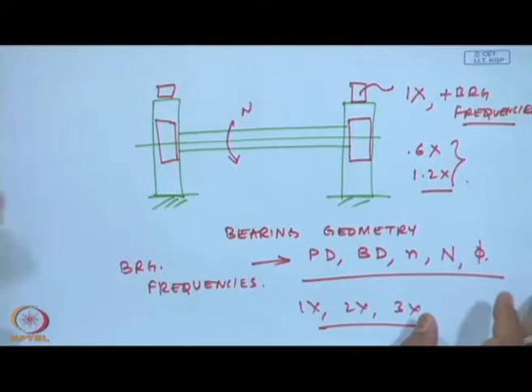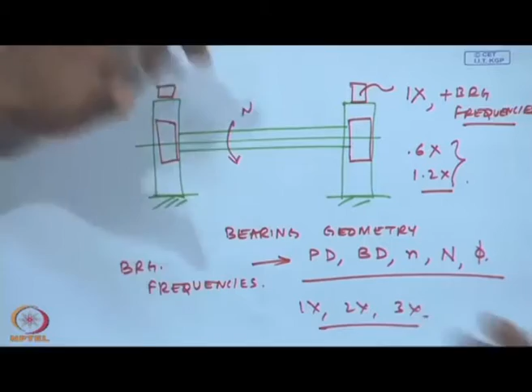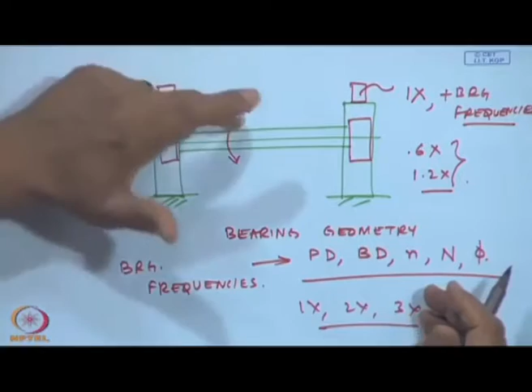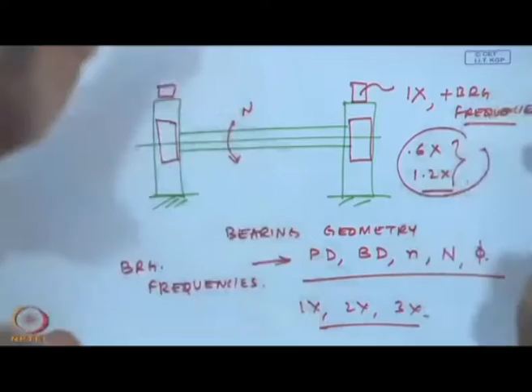And that is again why you may be wondering, well, I am always putting my transducers on the bearing mounts. What if the bearing frequencies are contaminating or mixing with my actual shaft defect frequencies of misalignment, crack, unbalance? That will not happen because they are at different frequencies. The bearing frequencies themselves are at a different value compared to the shaft frequencies, and that is actually helping us. Like I told you, in spectrum analysis every peak in the vibration spectrum corresponds to a particular defect in a particular mechanical element. It could be a bearing fault, a shaft fault, an unbalance, a gearbox fault. They are all different frequencies, and that really saves the work for us.